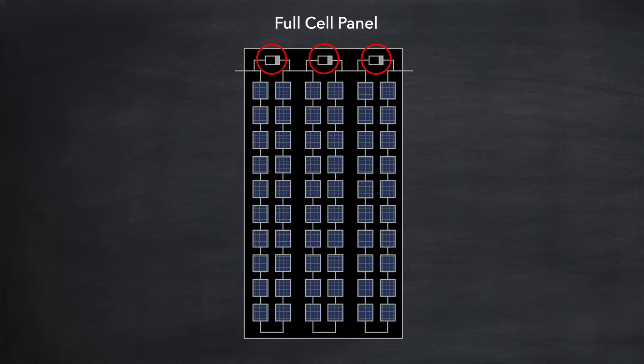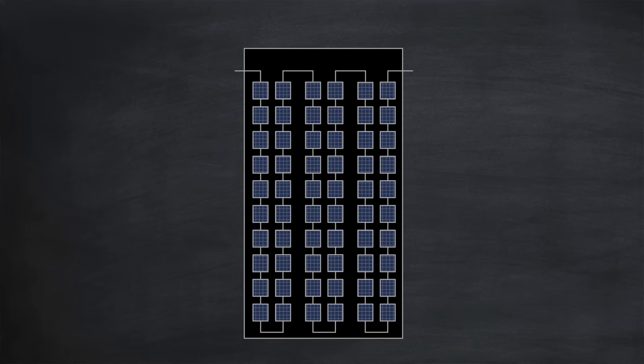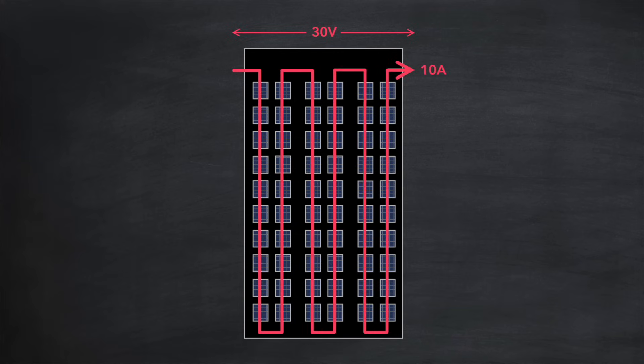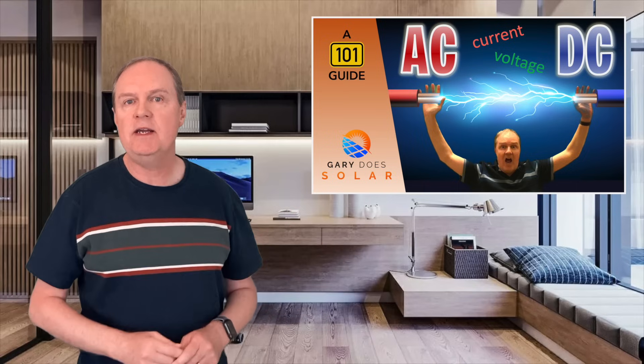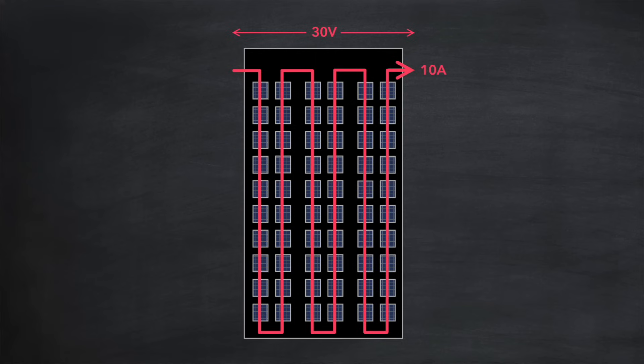The three components at the top of the panel are called bypass diodes, and they play an important role in shading management, which we'll talk about later. If we ignore them for the moment, you'll see that all the solar cells inside the panel are wired together in series. Each cell has a voltage of about half a volt and will generate varying levels of current depending on the amount of sunlight shining on it. These voltages add up to give a total panel voltage of 60 times half a volt, which equals 30 volts. If the panel is in full sunshine, we could expect a current of, say, 10 amps flowing through the panel. So with 30 volts and 10 amps, that gives us a total panel output of 300 watts.